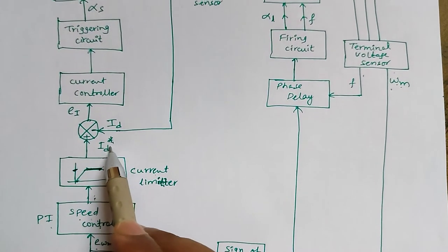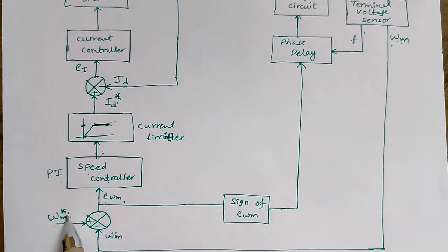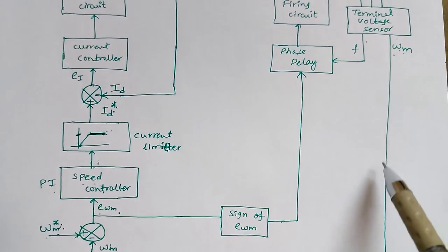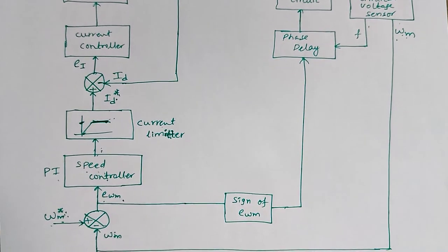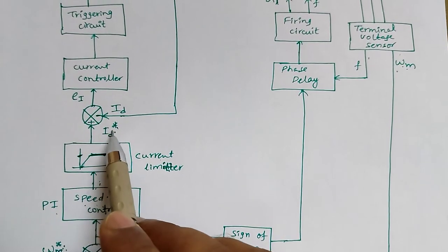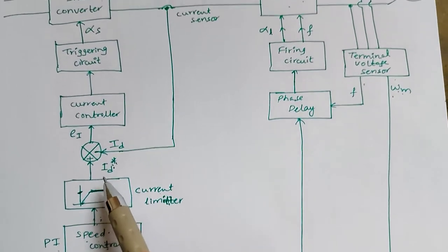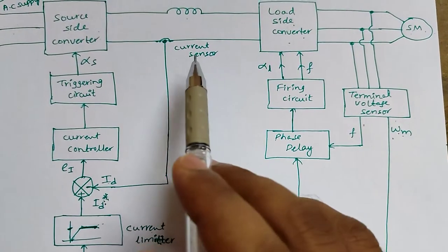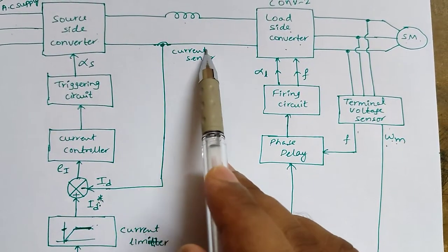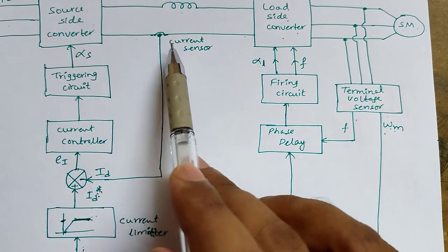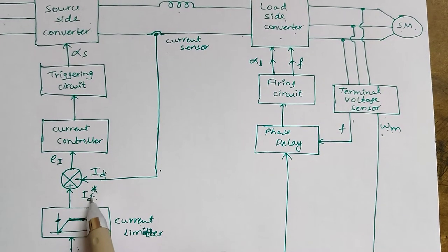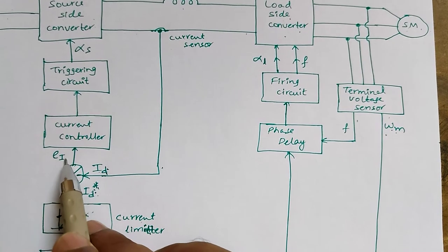So from the reference speed we obtain the reference current. The reference speed is compared with the actual speed obtained from the rotor position sensor or terminal voltage sensor. The difference gives the speed error, and by processing that error through the speed controller we get the reference current. The reference current is then compared with the actual current obtained from the DC link, where a current sensor measures the actual current. The difference between the reference current and actual current gives the error in current.